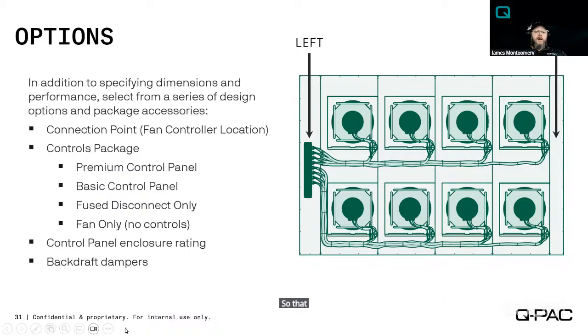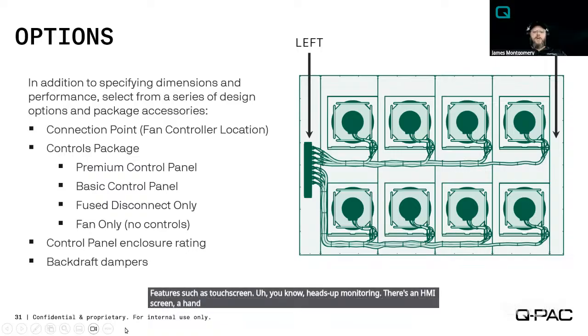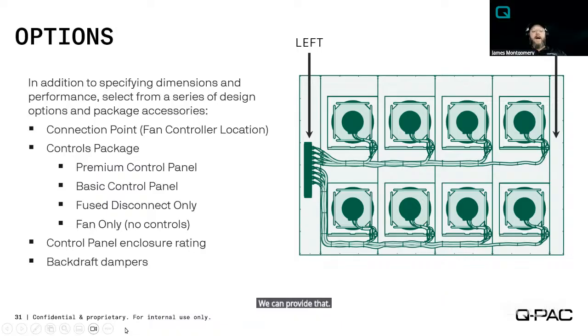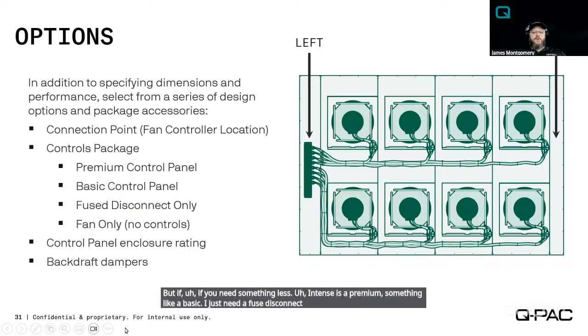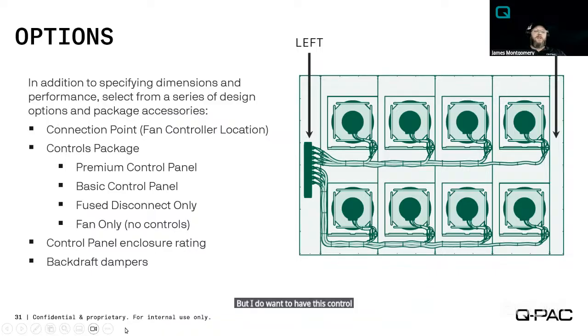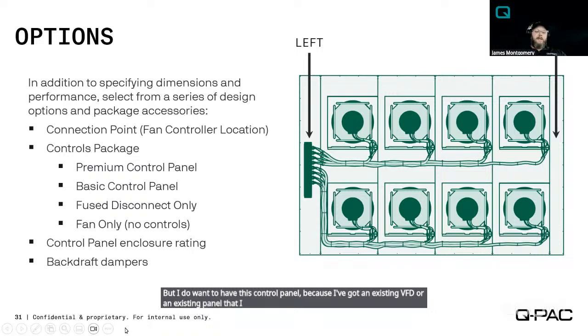So that connection point. Also, different controls packages. So in order to be a full-fledged solution, we want to be able to fit into anybody's building in any airstream. We do have a premium control package. If someone needs features such as touchscreen, heads-up monitoring, there's an HMI screen, a hand-off auto switch, almost like a bypass, physically on a panel. If you need that, or you need a fuse disconnect, we can provide that, and that includes things like BACnet and, like we talked about, IP. But if you need something less intense than the premium, something like a basic: I just need a fuse disconnect. I don't need all the additional BACnet features, but I do want to have this control panel because I've got an existing VFD or an existing panel that I want to replace, and we provide that.